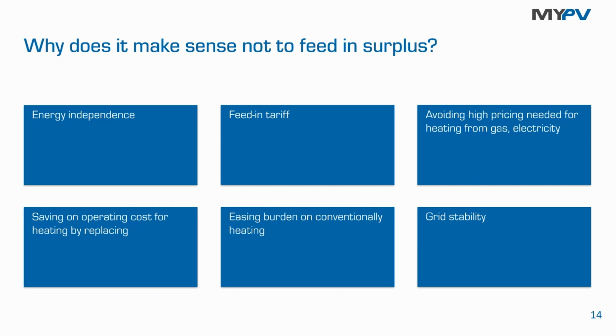Why does it make sense not to feed into the power grid? Maybe you have a feed-in tariff that is not attractive. Maybe you get less money for feeding into the grid than you have to pay for, let's say, gas. And then it's immediately interesting not to feed into the grid, but to use this kilowatt hour of energy for heating. You replace the gas one by one immediately, and then you have an economic saving, a monetary saving here.